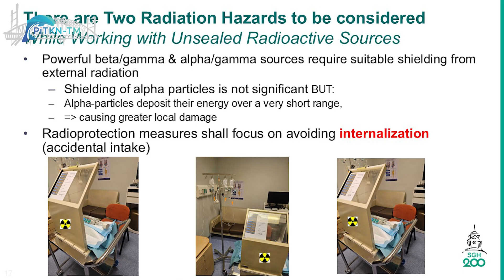Something like this will not work for 511, okay? For PET imaging or iodine-131, it won't, because you need much thicker lead because of the higher half value layer, higher tenth value layer for iodine as well as for fluorine-18. But it works perfectly for the low energy alpha and beta nuclides, okay?